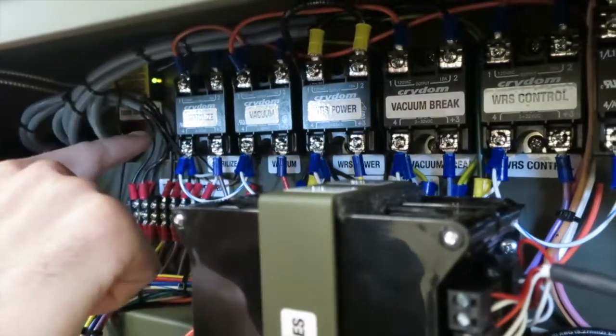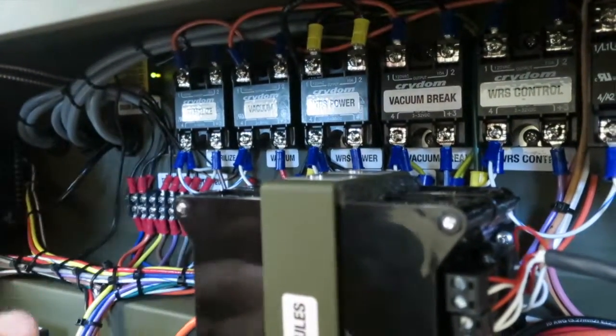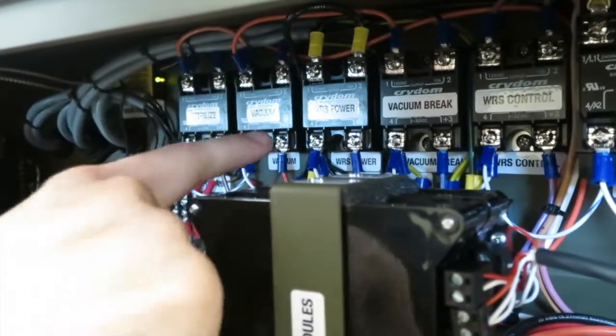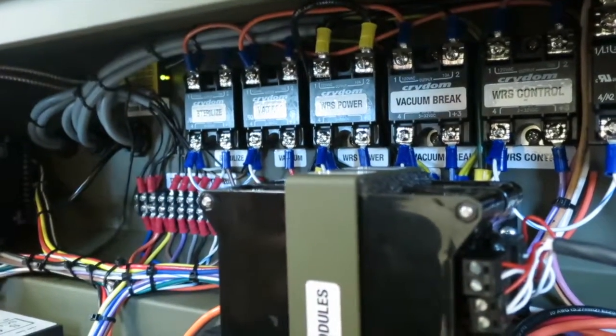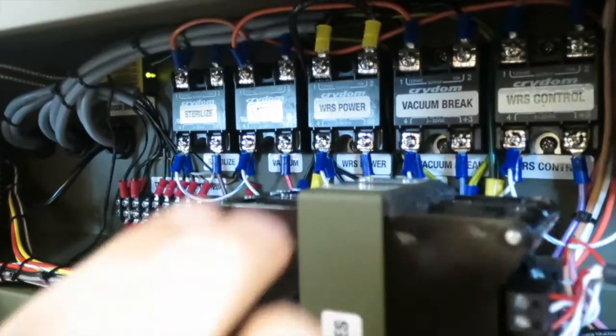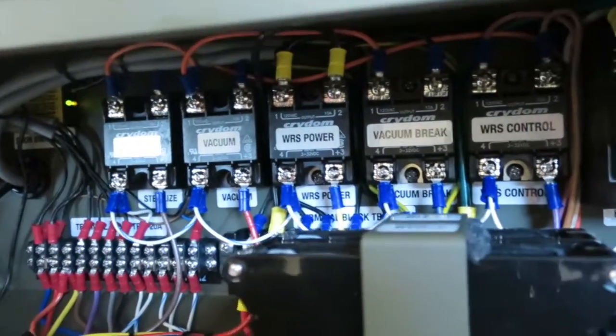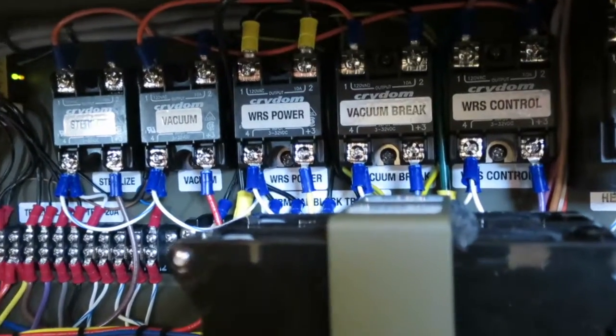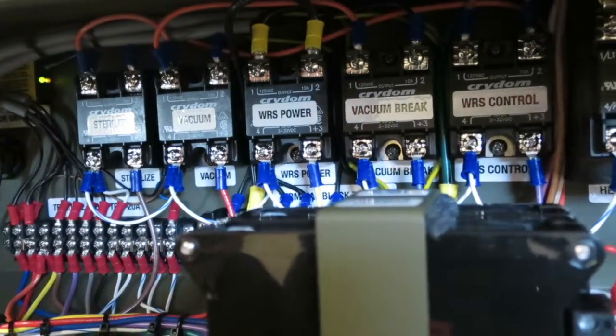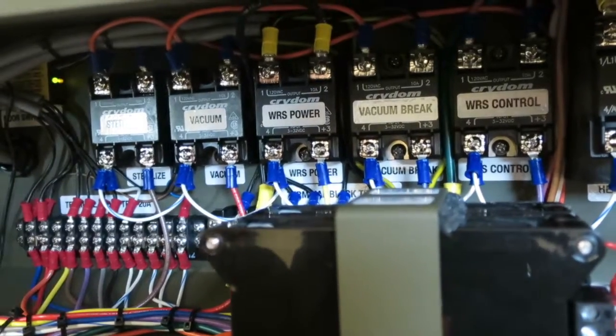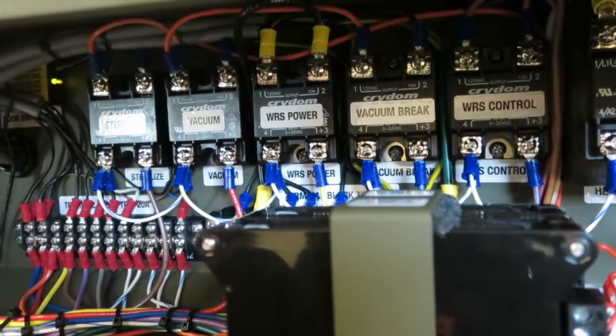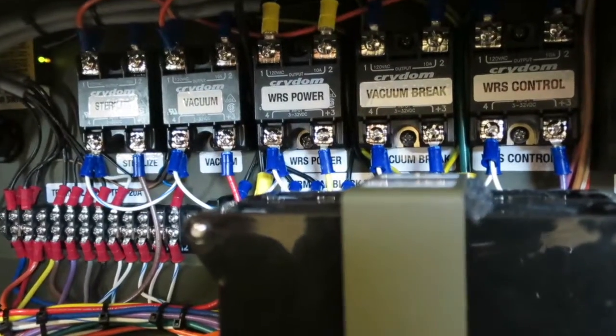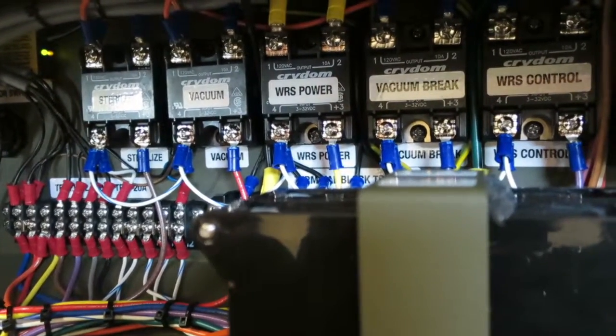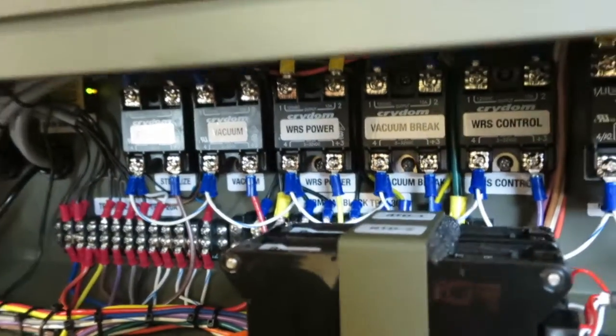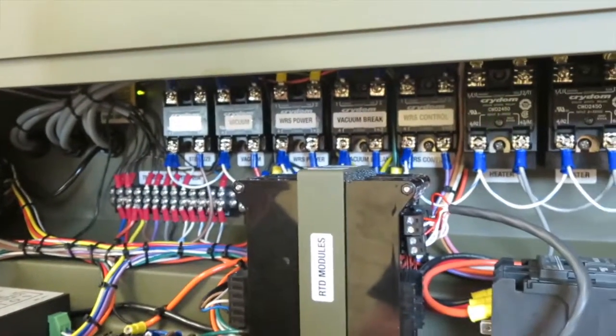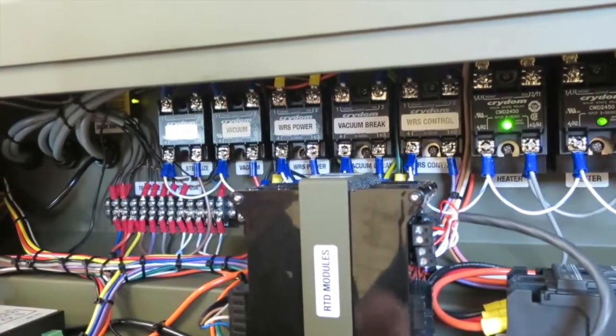solid state relay 1, the vacuum valve, which is solid state relay 2, the water recovery system power. This is a little unique. Remember I mentioned that the sterilizer main unit supplies power to the water recovery system. That water recovery system power, it's always sending power down there. So when this unit is on, that's actually live, so that when you press the toggle switch to send water up to the sterilizer main unit, you can go ahead and operate the pump and pump water up to the sterilizer main unit.